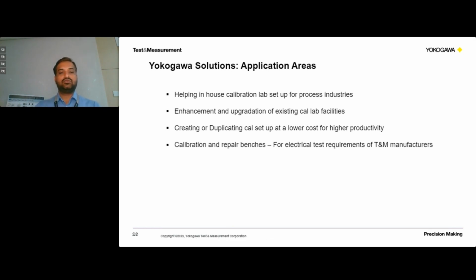And these are the instruments which are useful to have in calibration and repair benches. If you are a T&M manufacturer, manufacturing instruments such as energy meters, panel meters, panel indicators, voltage meters, current meters or clamp-on meters, those kinds of products, these are must-have products for your electrical testing requirements. You can do first-hand checking, production quality testing or in-house lab testing for your products. And if you are looking for a new calibration lab setup, we'll be able to help you with these products, starting from the consultation to the full-fledged installation.